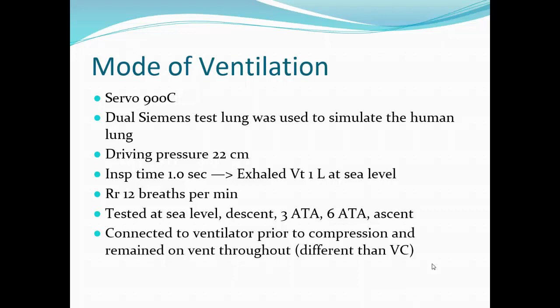He basically hooked them up to the ventilator before they started the treatments, and then measured the tidal volumes. And you could stay on this ventilator during ascent and descent without the need to disconnect and bag them on the way up or down. And he found that the respiratory rate and exhaled tidal volumes remained constant during all 5 test conditions. No adjustments were needed. This is an older paper I found from 2005. As of that time, he treated 9 patients, or 25 treatments, using pressure control ventilation with no untoward events.